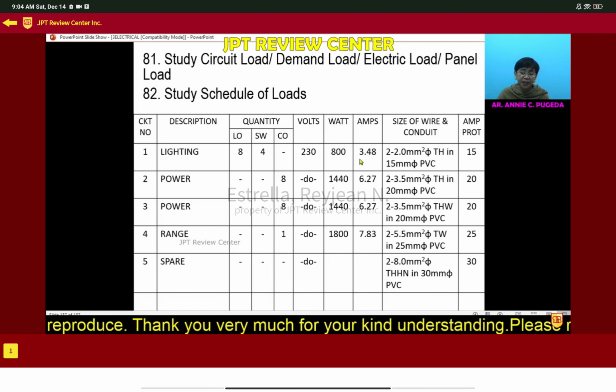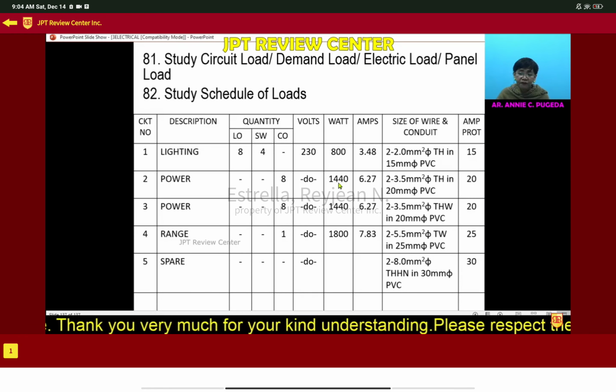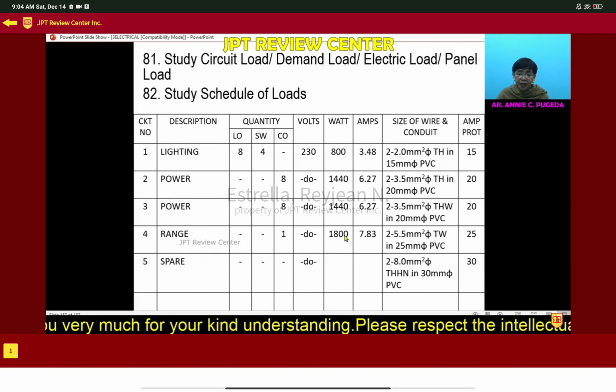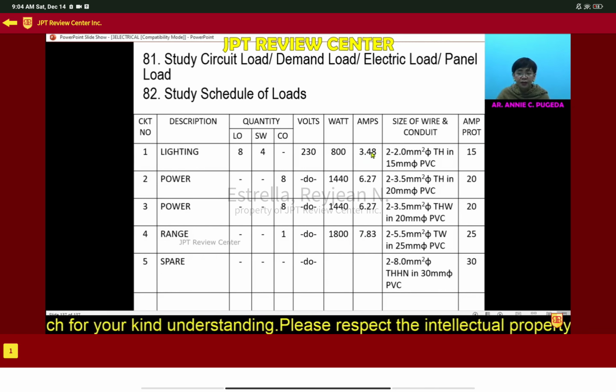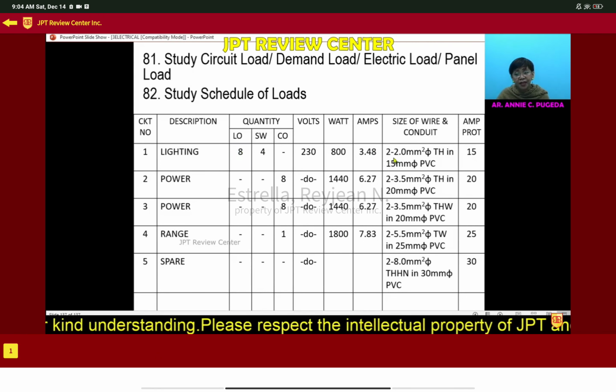1,800. How do you know the amps? Simple lang: 800 divided by 230 is 3.48. 1440 divided by 230 is 6.27. 1,800 divided by 230 is 7.83. Sa walong lighting outlets mo, ayun na ang size niya.